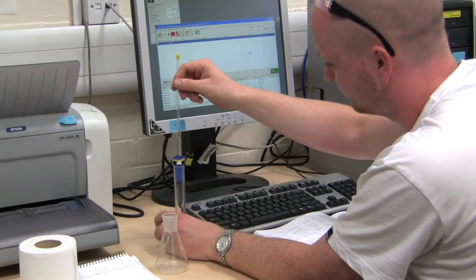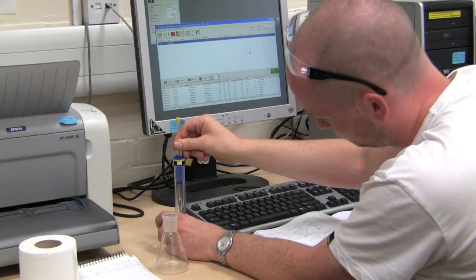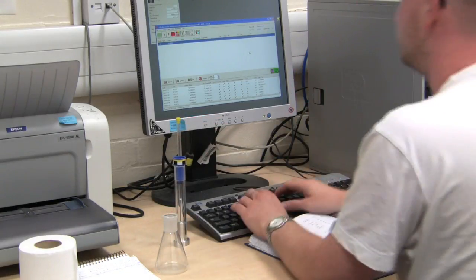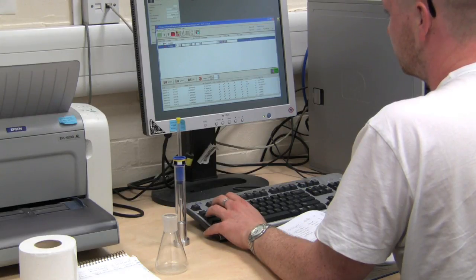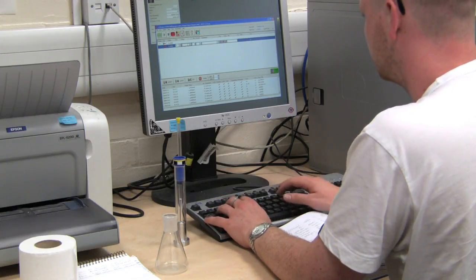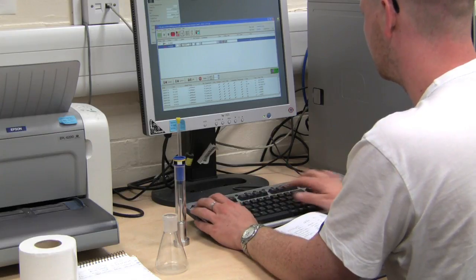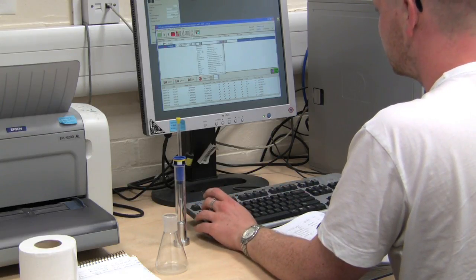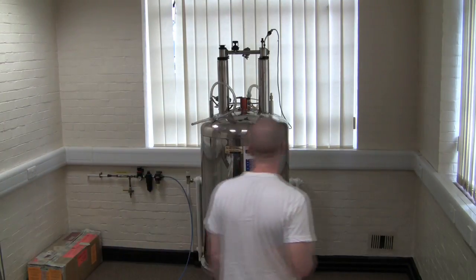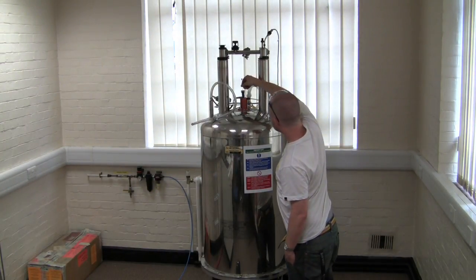After cleaning, the sample tube containing the sample is loaded into a spinner. A spinner houses the sample tube during the spectrum acquisition and protects it, allowing it to be rotated within the coil. The details of the sample to be run are entered onto the operating computer. The sample in the spinner is placed in the instrument above the magnet and lowered into the magnetic field on a cushion of compressed air.